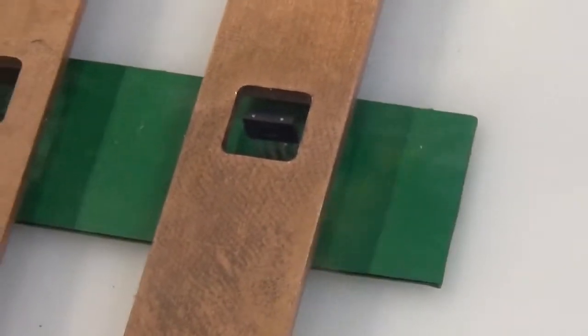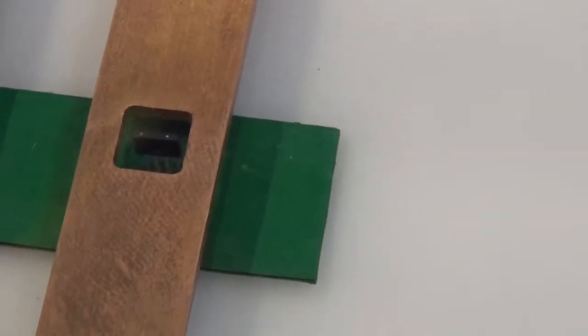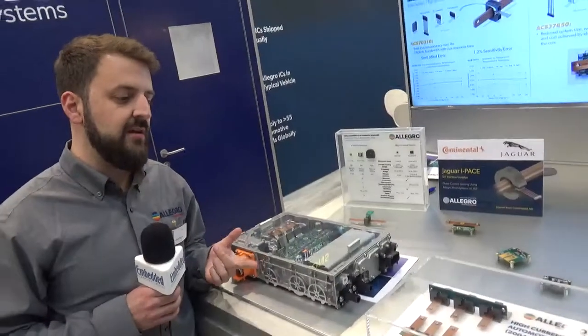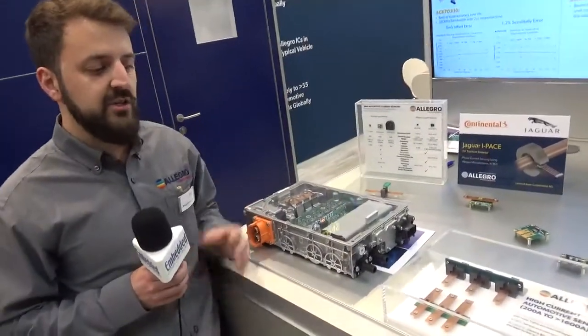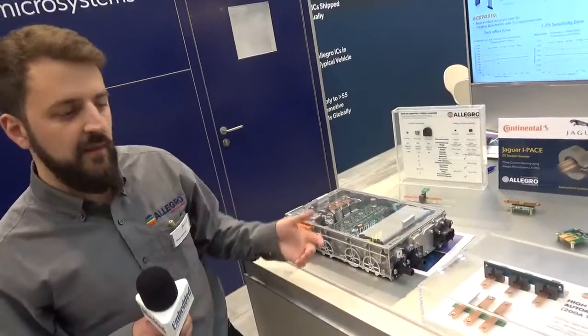It has up to 20 times the sensitivity of Hall. So now we can measure much smaller magnetic signals, meaning we don't need that magnetic core to concentrate the field anymore. We can just measure the small fields generated by current in the bus bar.